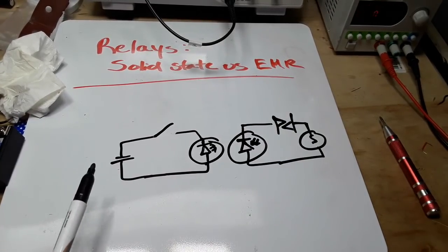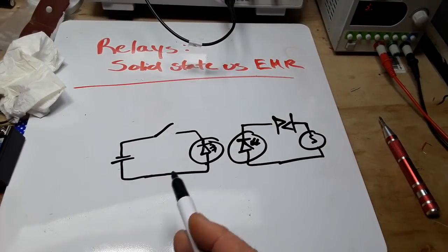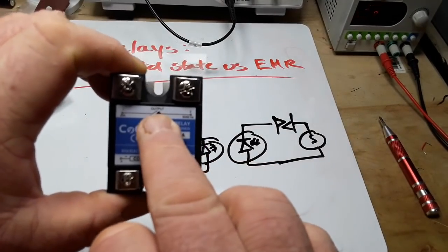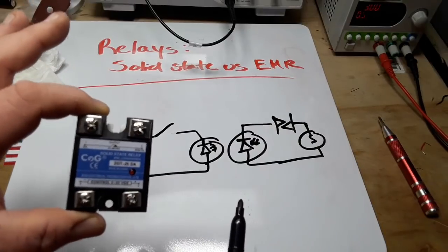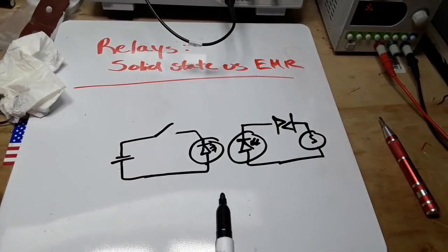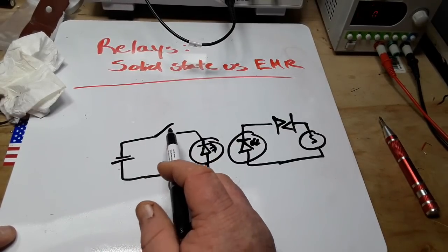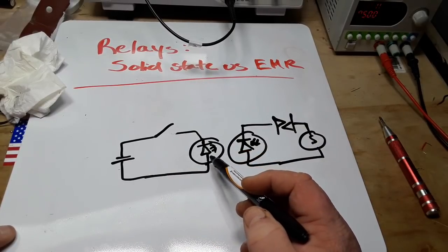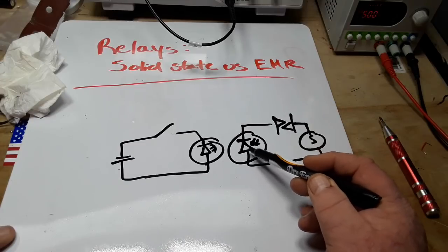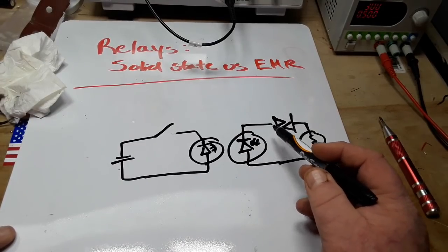Now here's a simple diagram of our solid-state relay. This one is a particular one for AC. Your solid-state relays are generally either specified AC or DC, unlike electromechanical relays, which can work either way. In this case, on the control side, we have a switch that basically just turns on and off an LED. Then we have the photovoltaic cell which receives that light and energizes a triac that switches the load on or off.